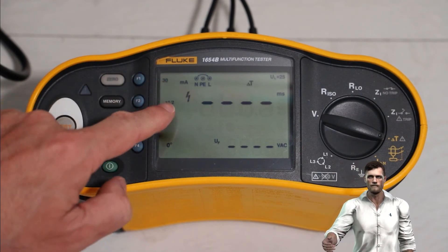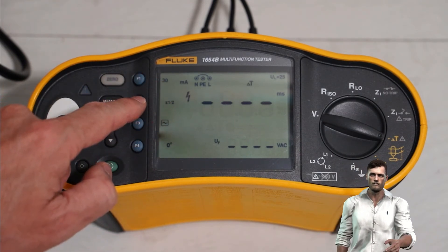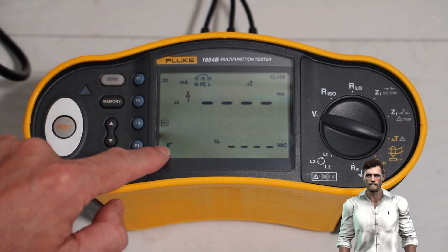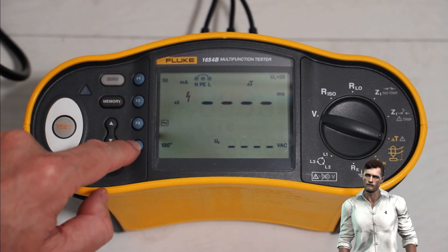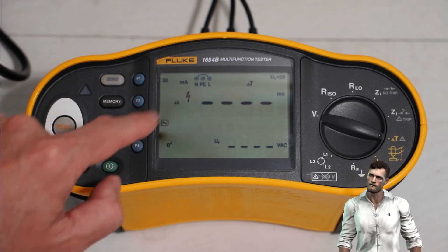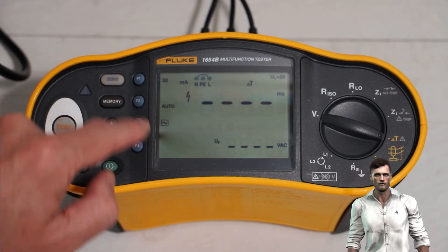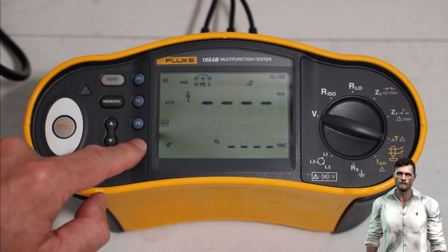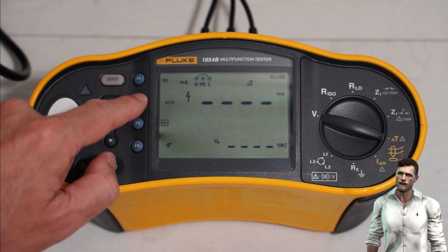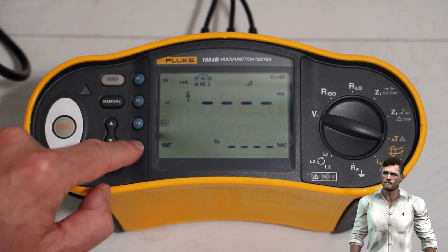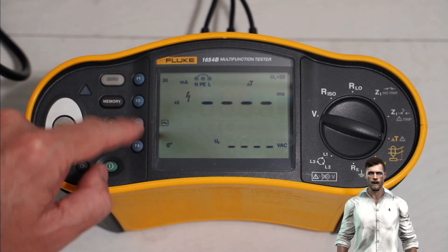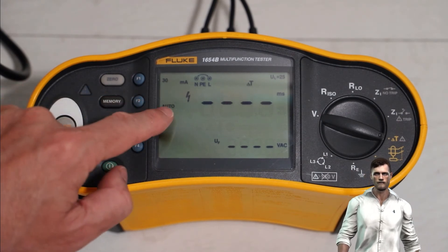Next, with F2, I am going to choose the leakage current that we are going to use to carry out the test. We can select among several values, for example half, which means that the equipment will generate a leakage current equal to half the nominal value of the differential protection. We can also choose one time and also five times, and finally we can select the auto option, and in this case the equipment will apply all the above currents sequentially. For this demonstration, I will leave it in auto mode in order to do a full differential test.